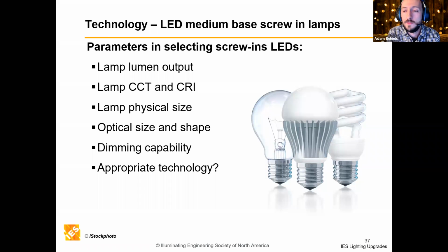The last option is the medium base LED screw-in lamps. When selecting these, look at the lamp lumen output. What are you replacing, what's the incandescent equivalent? Try to meet that lumen output wherever you can. What's the color temperature and the CRI? Try to hit the existing color temperature, usually if it's incandescent you want to be in the 2200 to 2700 range.